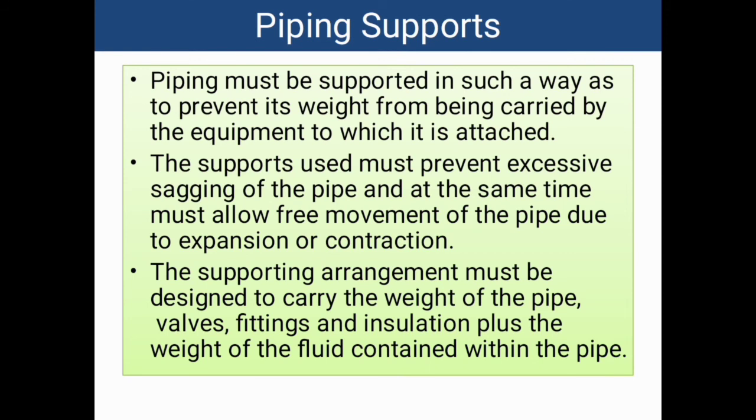Piping supports. In the first diagram we can see the piping layout. There are several pipes going here and there. For each and every pipe, we have to provide support. Otherwise, it will bend or it will be damaged. While designing a support, we have to include the weight of the pipe, the weight of the material, the thermal expansion, everything. Also vibration.